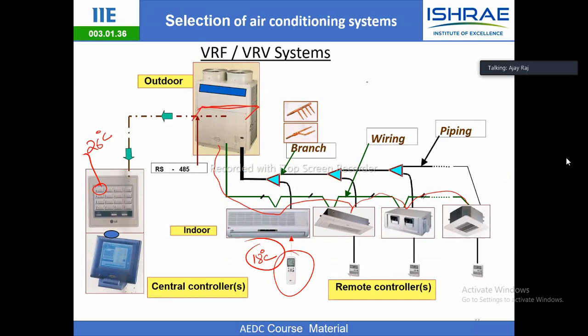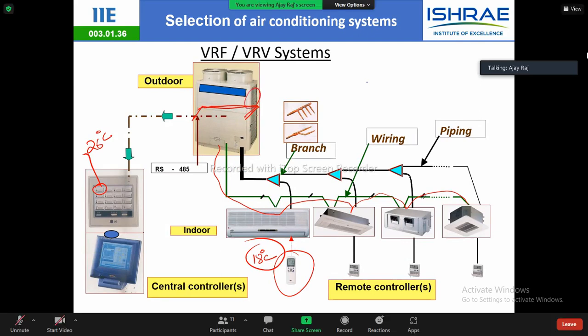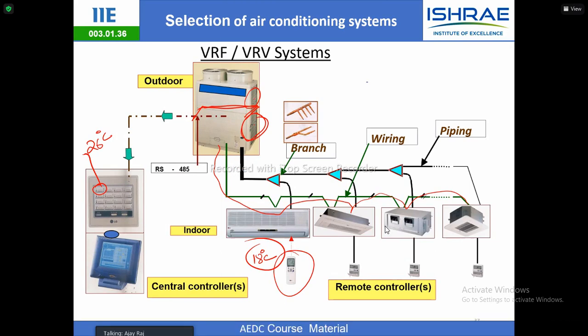So what happens is 50% of the time this part will do cooling and the other will do heating. When it does heating, whatever moisture or ice formation has happened gets removed, and then it switches over. So your outdoor unit continuously goes through heating and cooling cycles. I hope that's clear.